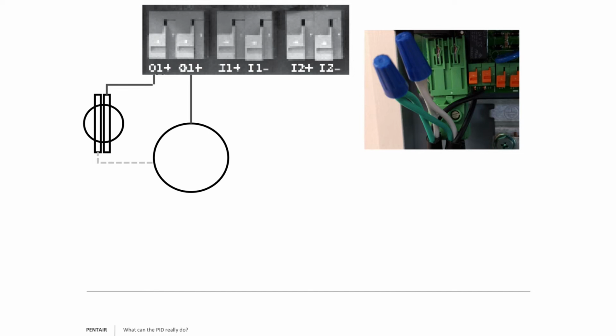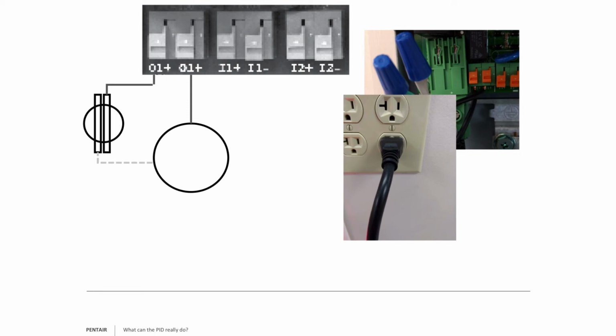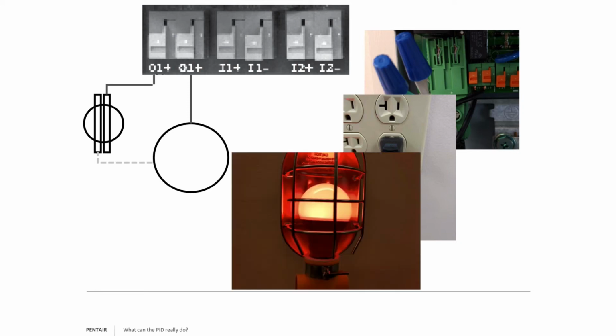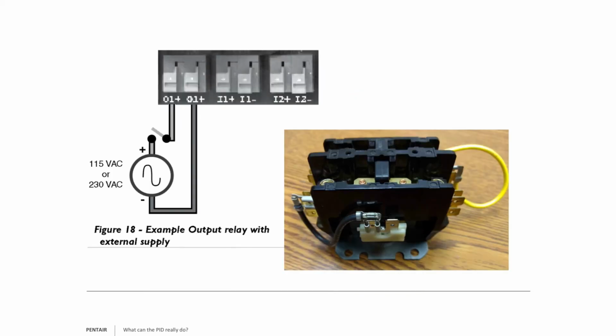So we have it wired up here. We have it plugged in, so now we have the circuit energized. So when that unit goes into fault, that relay would close and we would see our red light giving us an indication that the pump has faulted. Or maybe it's a green light and it's a run condition letting us know that the pump is running to our satisfaction.